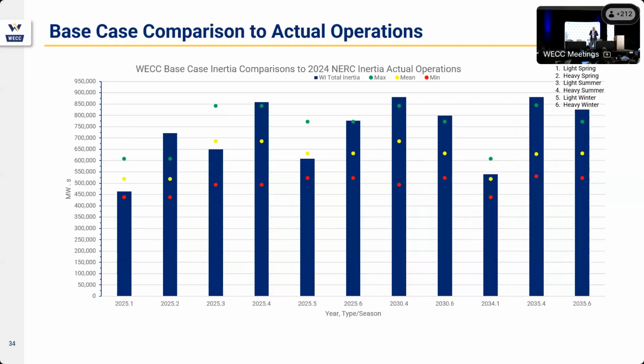What this is showing is if we look at the minimum inertia levels, the minimum in real time very closely matches the minimum in the planning cases for the light spring case. But if you go across the years, our planning cases show inertia is increasing. Our data shows inertia is declining. Our forecast data of resources show inertia is declining, but our transmission planning cases don't reflect that. We're showing generally increasing inertia in all but the light spring cases.